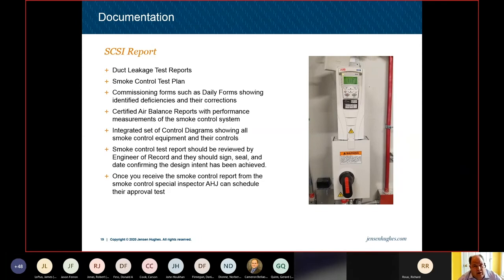There's a smoke control test plan that gets developed that tells everyone involved, including the fire alarm contractor, what are we going to be testing? How are we going to test it? Coordination of all those various subcontractors and disciplines makes sure we have our I's dotted and T's crossed and don't miss things, such as no one monitoring the damper status for smoke control positions, or how we're proving the stair pressurization is on. There's a whole lot of different things that go into that, and that should all be brought out early in the test plan. But that test plan gets included in the finalized report at the end of the job.